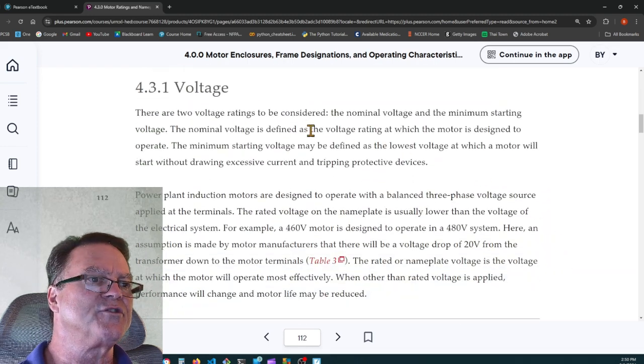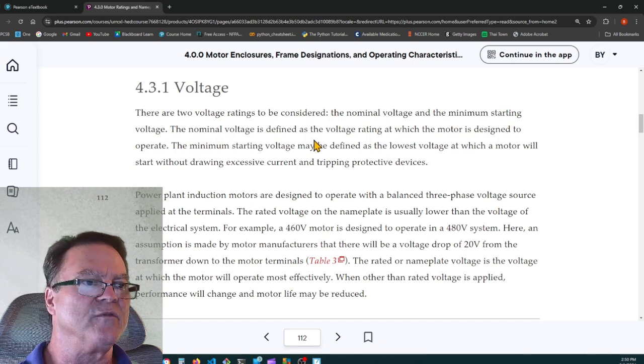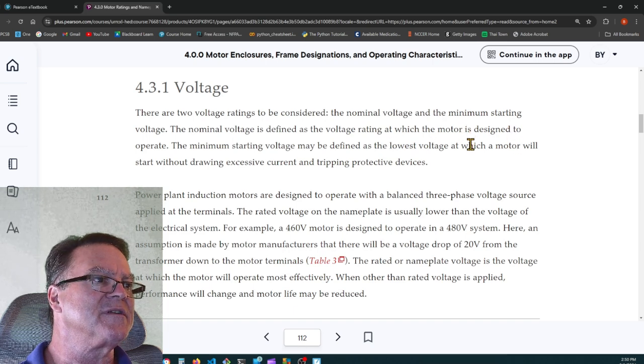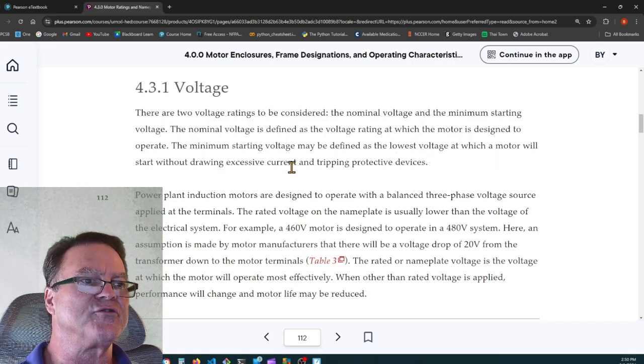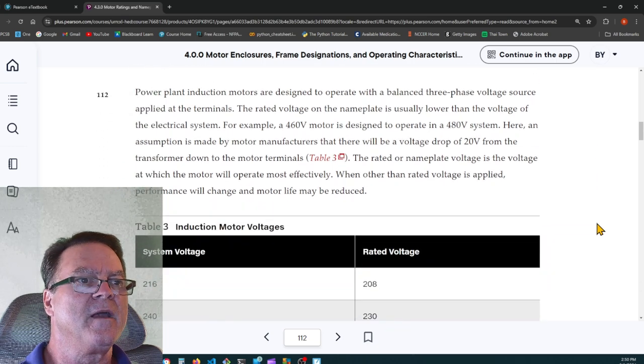So there are two voltage ratings to be considered: the nominal voltage and the minimum starting voltage. The nominal voltage is assigned as the voltage rating at which the motor is designed to operate. The minimum starting voltage may be defined as the lowest voltage at which the motor will start without drawing excessive current and tripping the protective device.